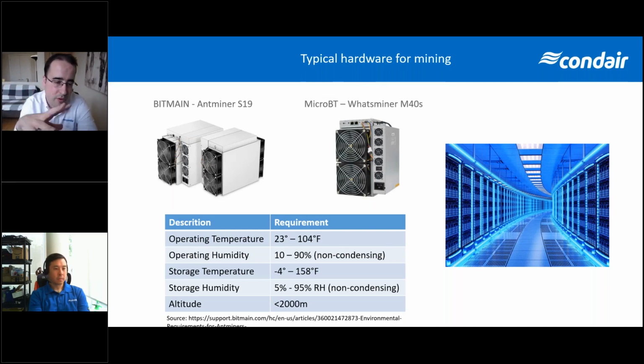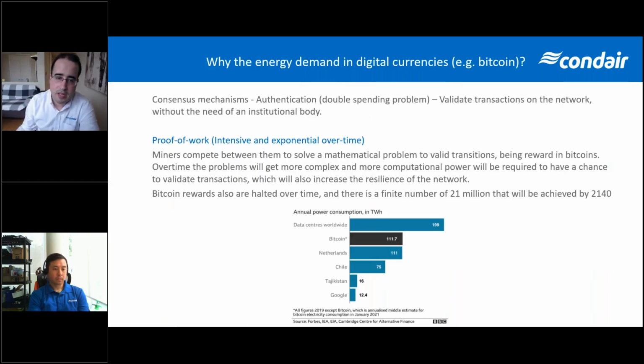So we can offer both our evaporative systems or our humidification solutions for cooling in the summer, or if you have free cooling in cold areas, then you need to humidify because it will probably even be less than 10% RH, and then you have a lot of static inside your data center. One of the big issues, as you can see in this graph from BBC, is that right now just Bitcoin is almost half, or actually more than half, of all data centers worldwide for electrical consumption in terawatt hours.